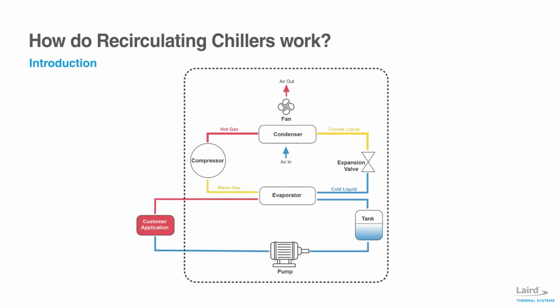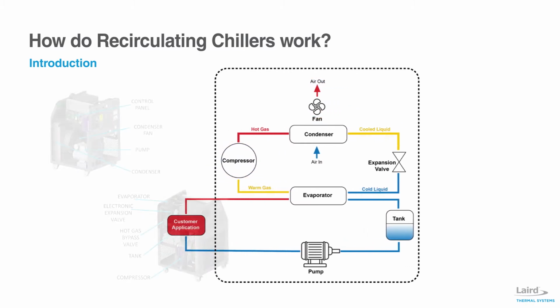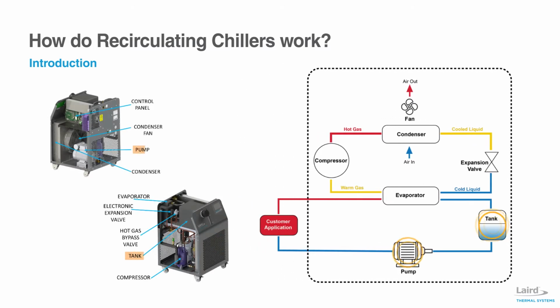Recirculating chillers are liquid cooling systems that control the temperature of water or water with glycol, antifreeze, in a liquid circuit, with little impact by the surrounding temperature. The coolant is recirculated using a high reliability pump. Heat from the coolant is absorbed by a durable compressor-based system and dissipated to the ambient environment. The main components include a tank, pump, heat exchanger or evaporator, compressor, heat exchanger, condenser, fan, and expansion valve, all housed inside a durable sheet metal casing.